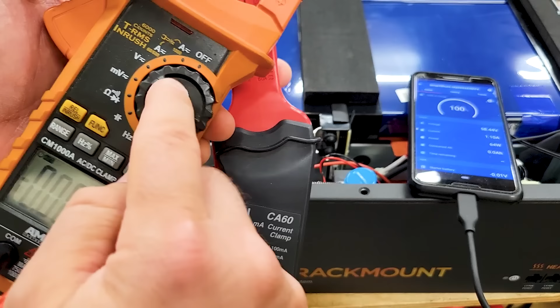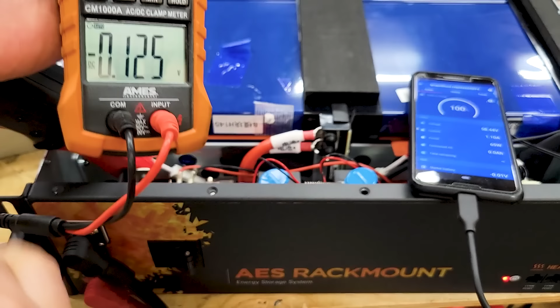While we're sitting here waiting, I pulled out this little amp clamp. The multimeter is set to voltage, but it's actually going to read amperage for us. I'm going to clip it on the little wire leading to the silicone pad. This is one decimal place off, so this is actually 1.2 amps going into the heating pad. This other one shows 1.1, so it's somewhere between 1.1 and 1.2 amps of current, and all of it is going to the heating pads to warm things up.